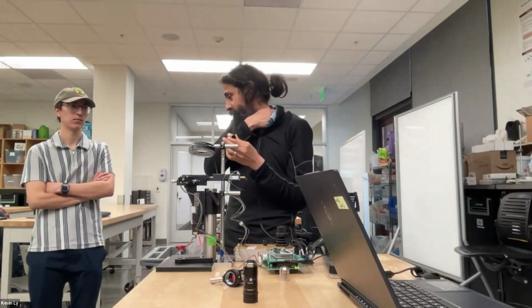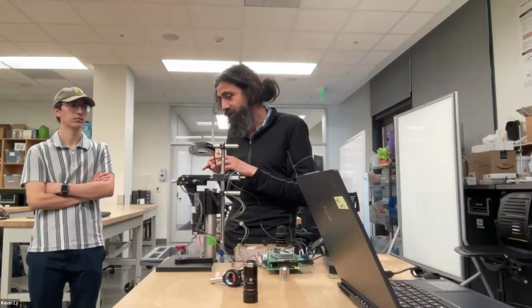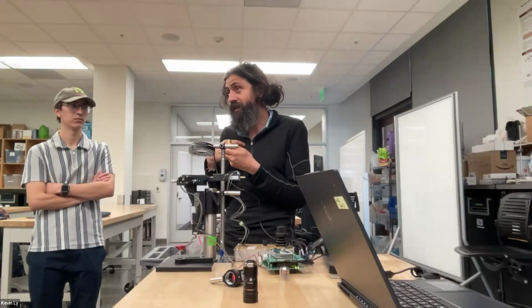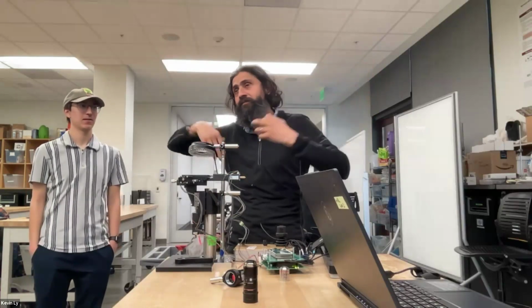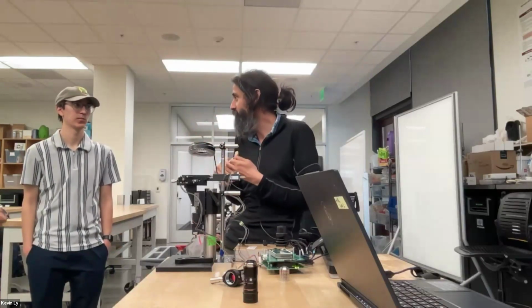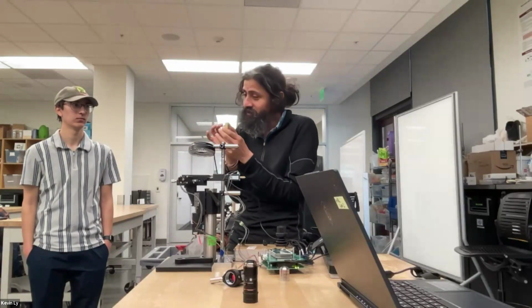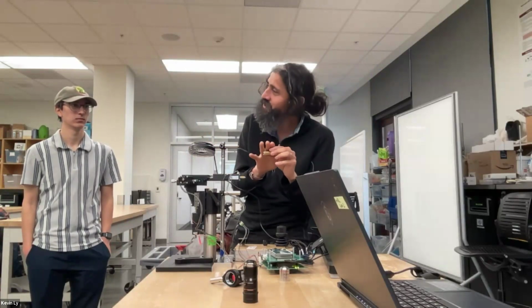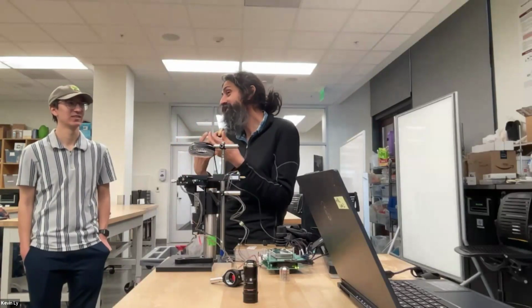And still, the last time I visited a factory in India that makes objectives, people have a mastery. It's all still done by hand. When I visited Zeiss, there is a dark room in the basement. I mean, imagine these giant factories pumping out all of these things. You would say there would be all these robots. No, there are people in a dark room who have honed the skill for 30, 40 years, because you align a little bit and you test it, and you align a little bit and you test it, and then you shim a little here, and they don't let anybody go in that room. And still, that's how we make objectives, because it's hard.